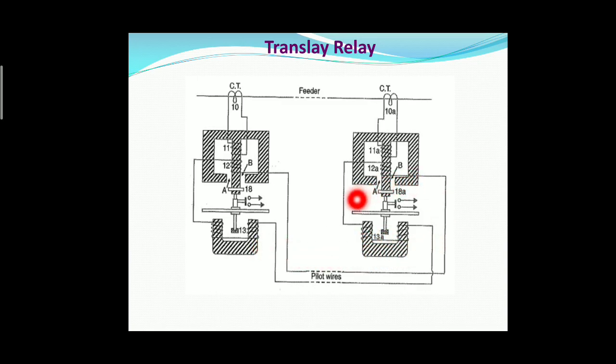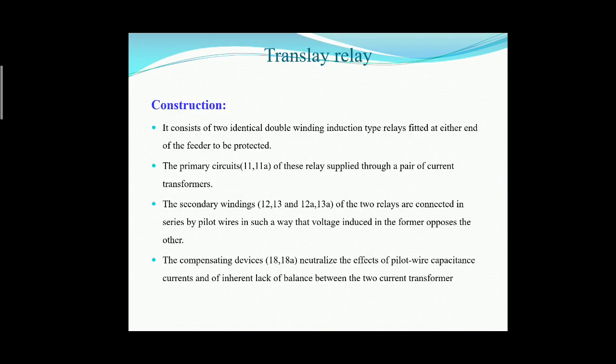13A and 12A are connected. The 12 and 13 and 12A and 13A of the two relays are connected in series by pilot wires, in such a way that the voltage induced in the former opposes the voltage induced in the other.